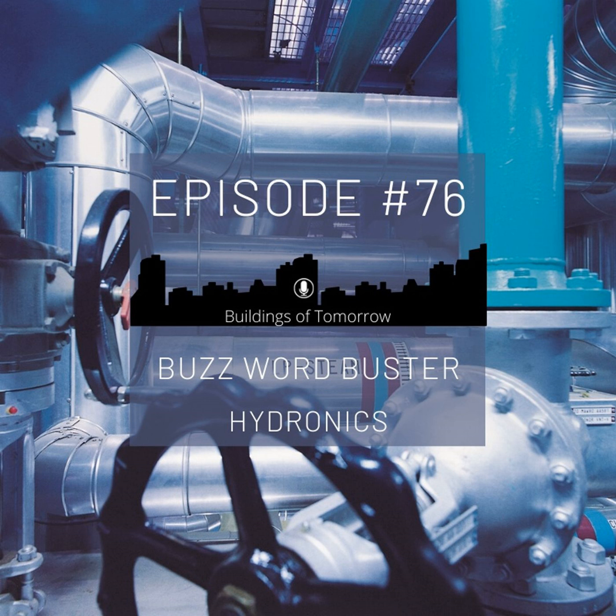Yes. So proportional laws, as we call them in the German-speaking countries, or in Europe, or affinity laws, as they are called in English-speaking countries, are basically laws derived from fluid dynamics theory. These laws apply to our hydronic setups, meaning our water-based circuits for heating and cooling, but they also apply in the same manner to our air streams in the ductwork. So we can apply these fluid dynamics laws with the medium that we normally work with, either water, cold or warm, or the air that we run through the building. And they are very important because they have a big impact on energy efficiency.